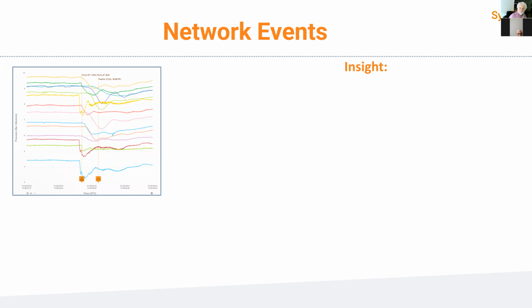When it comes to pressure transient events, we've got an example here in the top left. So you might find you have a pump stop, a sudden drop in pressure, which travels as a wave around the network. When you get a sharp change in pressure, I'm talking about something half a bar or bigger, either up or down, and happening in less than a second, normally something like 0.2, 0.3 of a second, it can be longer, that will travel as a wave around the network.